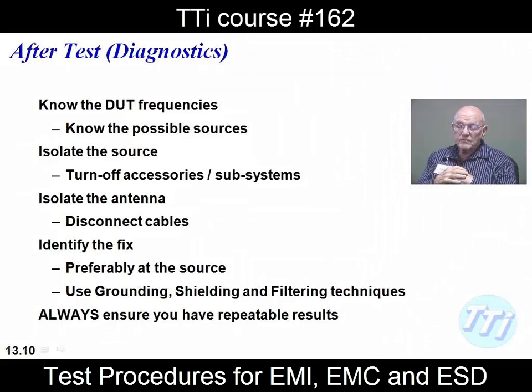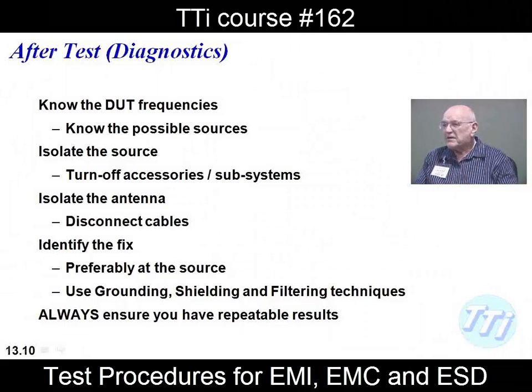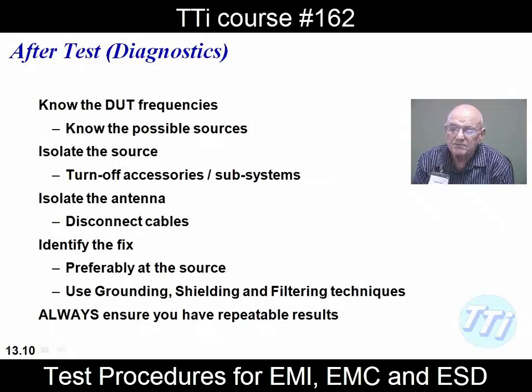And you also saw that one way to isolate the source was using the probes from Agilent that allowed you to eliminate the electric field and only measure the magnetic field. And they were pretty darn good. I suspect, I don't know about you, Jim, but are you going to go get a couple of those when you get back? We need some. Yeah, so you see what I'm getting at? For sure. That'll allow you to very quickly find and make troubleshooting changes and things of that nature.